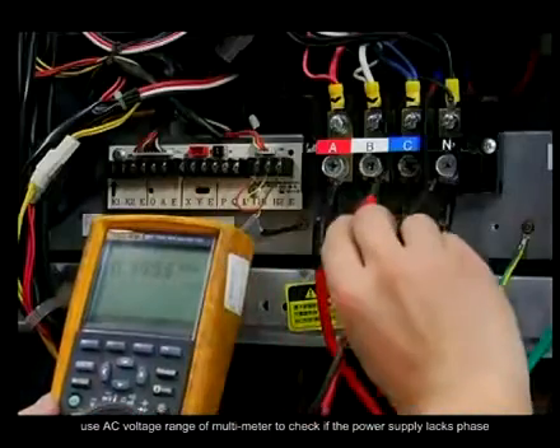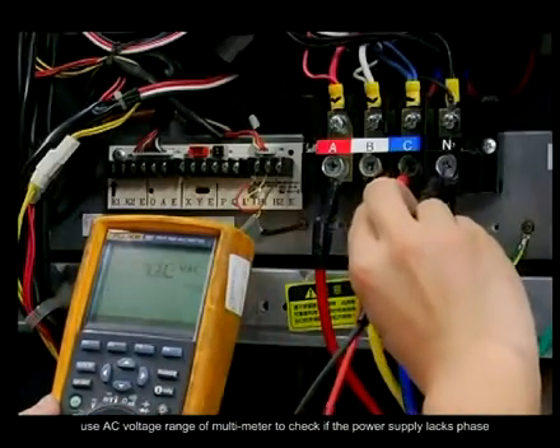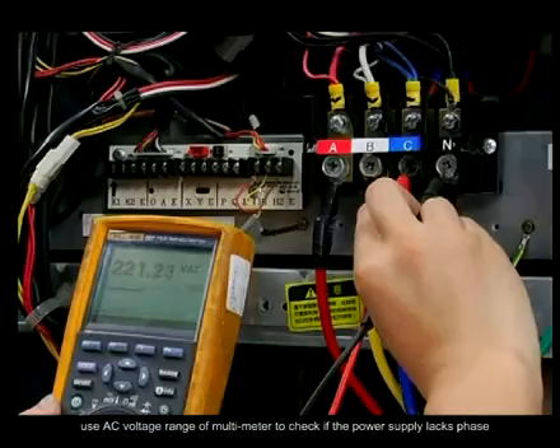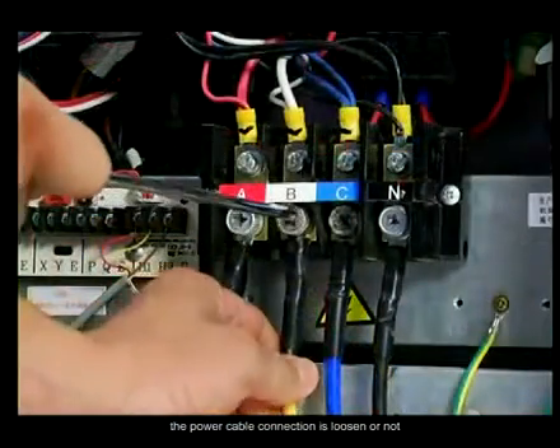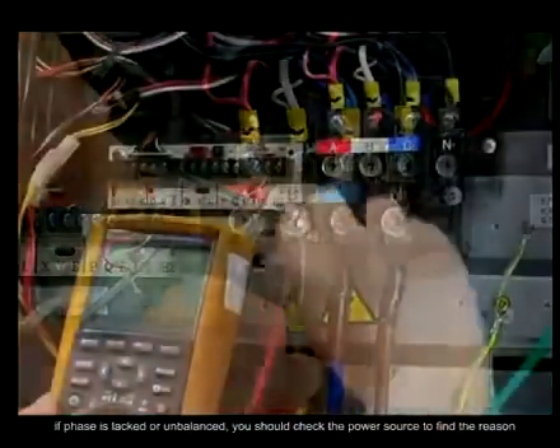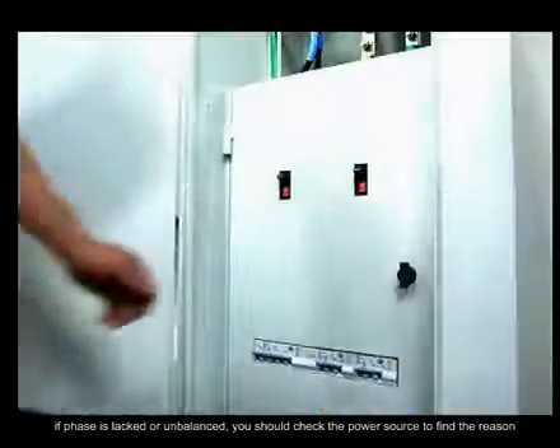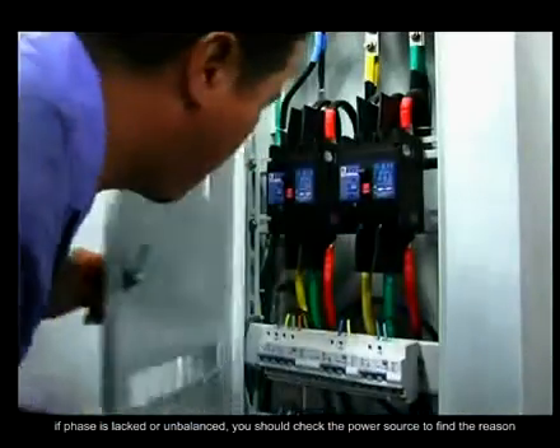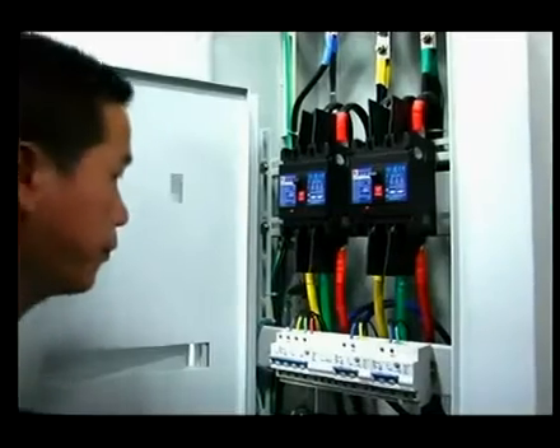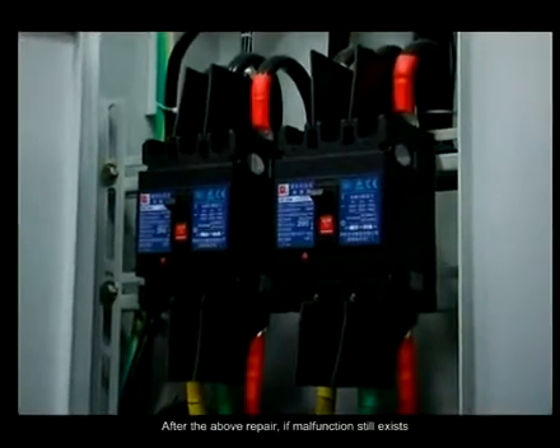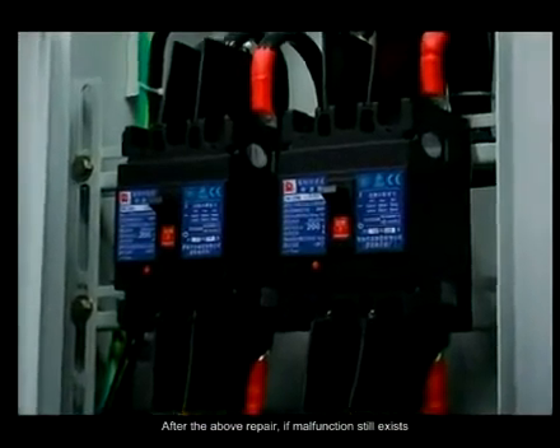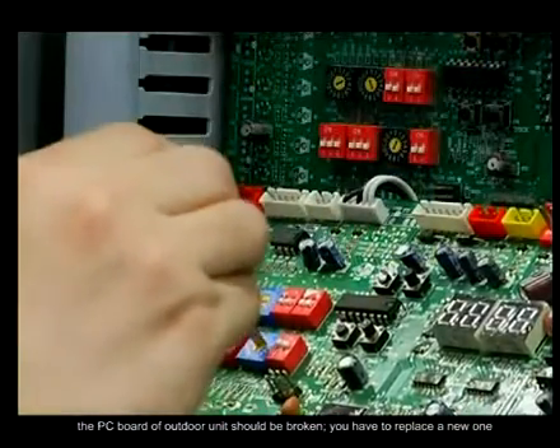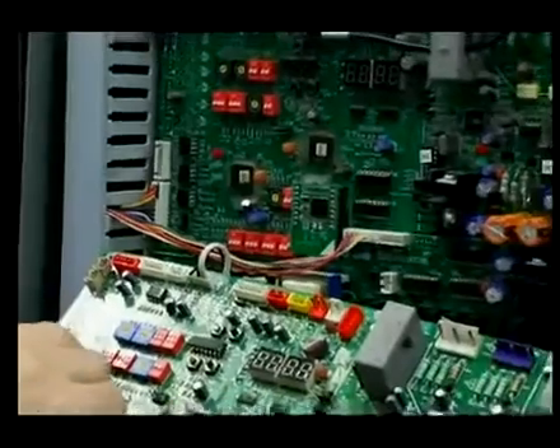Step 2. Use AC voltage range of multimeter to check if the power supply lacks phase, and whether the power cable connection is loosened or not. If phase is lacked or unbalanced, you should check the power source to find the reason. After the above repair, if malfunction still exists, the PC board of outdoor unit should be broken. You have to replace a new one.